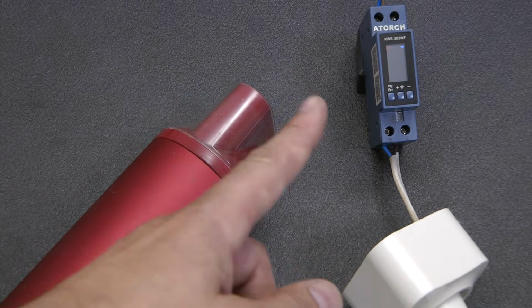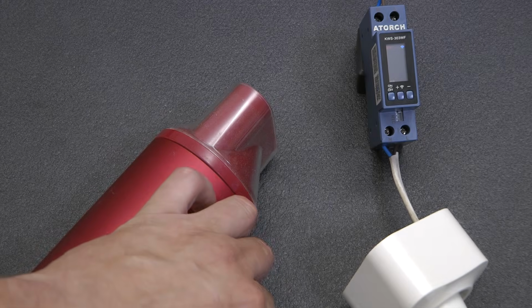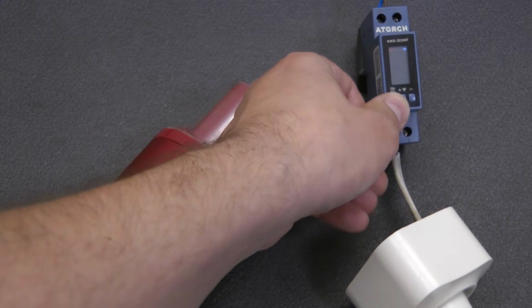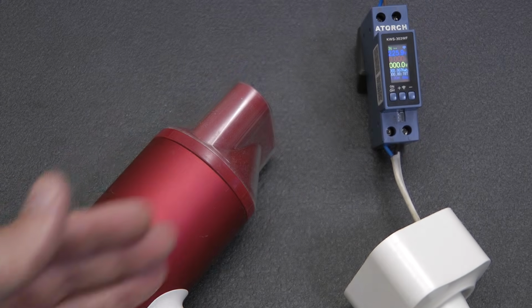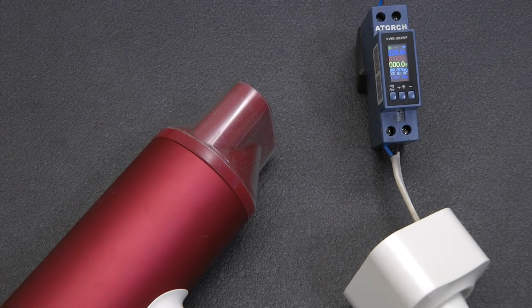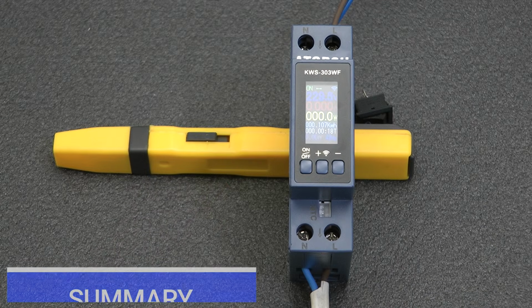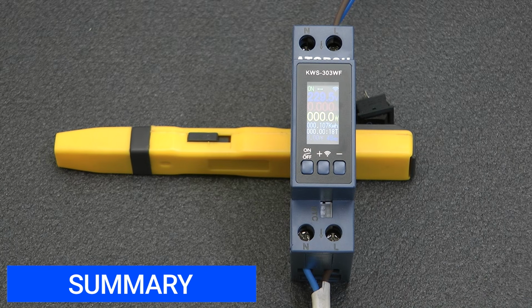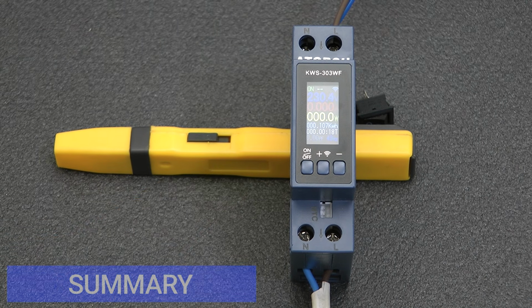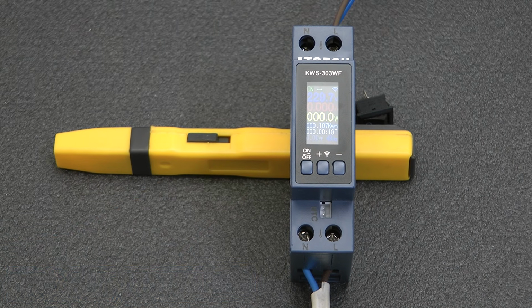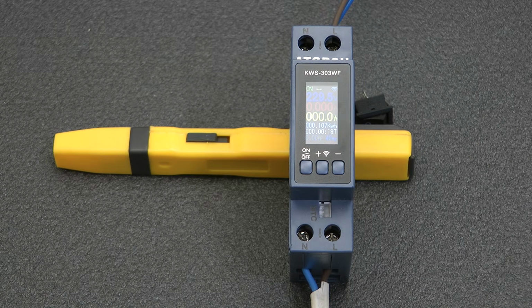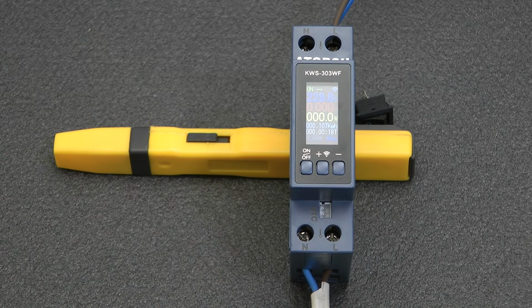But it is important to understand that this is a relay, not a circuit breaker, not an RCD, and not full protection for equipment against problems in the power network. Proper protective devices must still be installed before it. Overall, the relay turned out to be quite interesting. The main advantage for me is the display. You do not have to open the app every time just to check voltage, current, power, or total consumption. You walk up to the electrical panel, look at it, and everything is immediately clear.